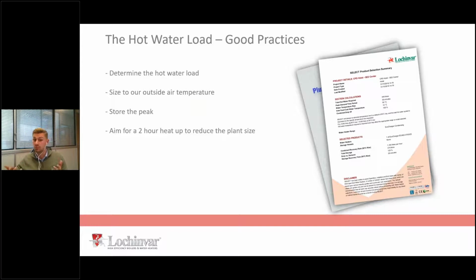Perfect. Also reduced our standing losses. Now what we've done is with the air source heat pumps, remember we need that minimum storage content. We want about 10 to 20 litres a kilowatt ideally, and to run a heat pump effectively, you want to turn it on and leave it on for a long period of time. You don't want it to cycle. So if you can aim for a 2-hour heat up time, 1 hour is fine. But if you can aim for a 2-hour heat up time at your design temperature, it means most of the time it's not actually a 2-hour heat up time anyway, because remember it's more efficient in the summer. But that air source heat pump is going to operate in a format that means it turns on, stays on for a long period of time. You get an enhanced efficiency from your compressors, and that enhanced efficiency completely offsets the additional standing losses for storing more water.